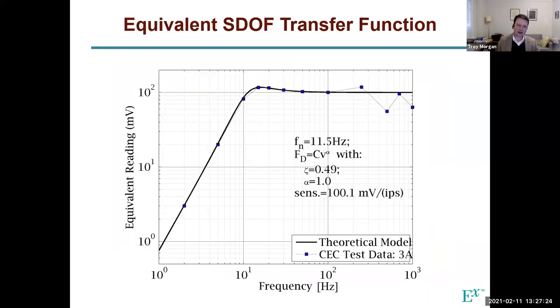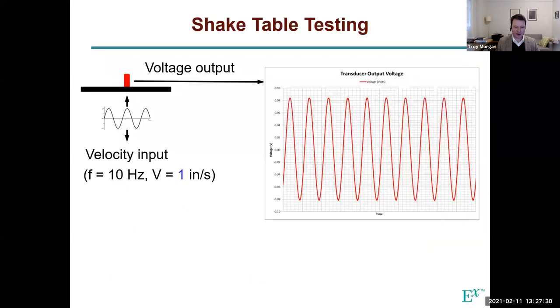And so we characterized this transfer signal over the range of frequency. We got the data in this range by running a test on the shake table and measuring the voltage output. So under small levels of motion, say 10 Hertz frequency but only 1 inch per second velocity, you get a perfectly harmonic output - harmonic input, harmonic output - that's a linear system.